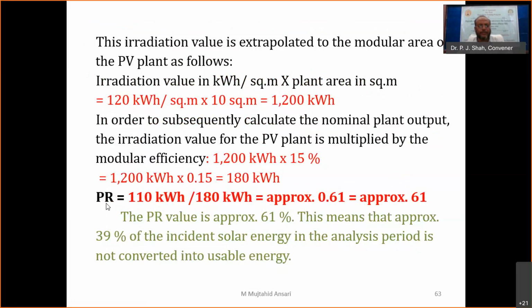By calculating the performance ratio, if it is in the range of 70 to 80, it indicates a certain loss. For example, here we have calculated the performance value as approximately 61%, meaning 39% of incident solar energy in the analysis period is not converted into useful form. This may be due to defects, power failure of the grid, or temperature variation. All these points affect the performance ratio, which indicates the proper analysis of a PV on-grid solar power plant.